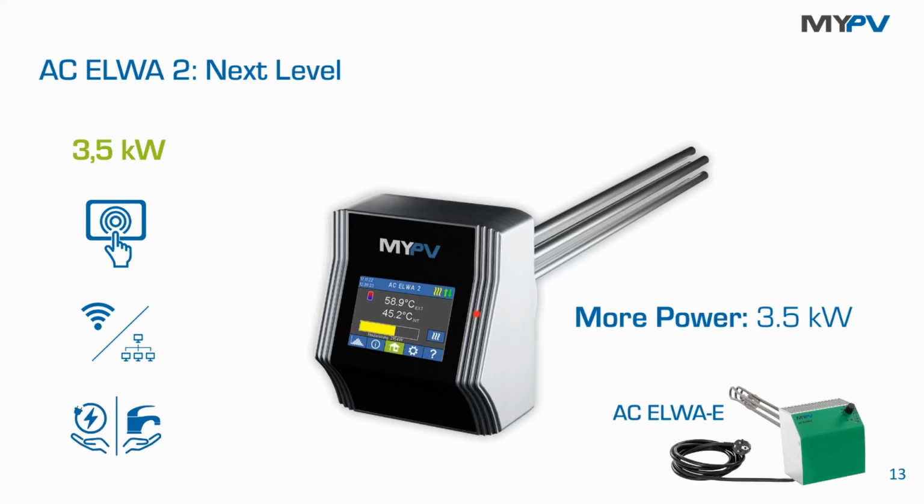Okay, 3.5 kilowatts is still possible with a 16 amp fuse. For a 3 kilowatt unit, it meant a current of 13 amps. It's, of course, slightly higher with 3.5 kilowatts, but it's still within the range that is covered by a 16 amp fuse. So more power, first of four main benefits.